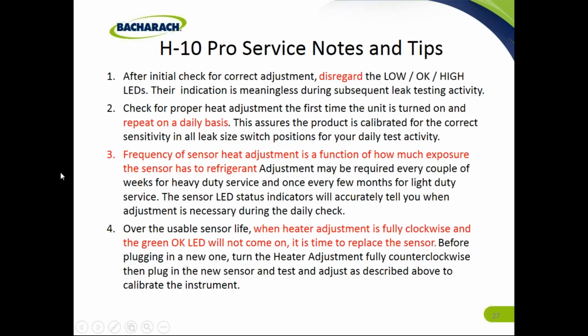So when you've been adjusting the heater adjustment up there in the upper right-hand side, and you can no longer go any further clockwise, and that green OK LED is not on, you have to replace the sensor. Before plugging in a new one, turn the heater adjustment fully counterclockwise, then plug in the new sensor and test and adjust as described above to calibrate the instrument.